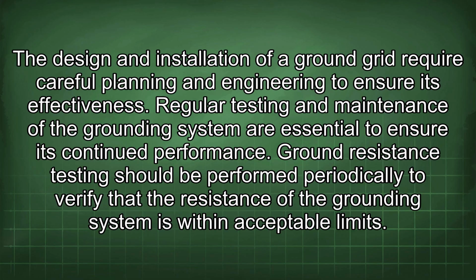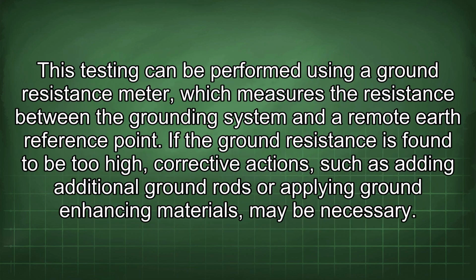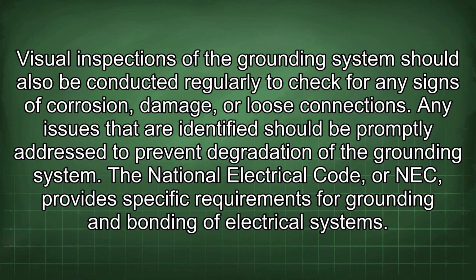Ground resistance testing should be performed periodically to verify that the resistance of the grounding system is within acceptable limits. This testing can be performed using a ground resistance meter, which measures the resistance between the grounding system and a remote earth reference point. If the ground resistance is found to be too high, corrective actions such as adding additional ground rods or applying ground-enhancing materials may be necessary. Visual inspections of the grounding system should also be conducted regularly to check for any signs of corrosion, damage, or loose connections. Any issues that are identified should be promptly addressed to prevent degradation of the grounding system.